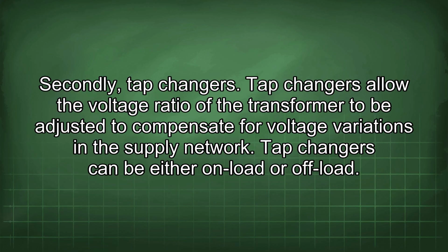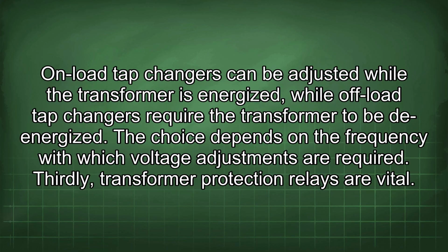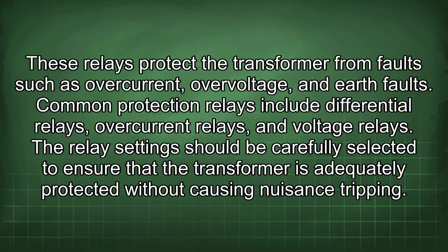Tap changers can be either on-load or off-load. On-load tap changers can be adjusted while the transformer is energized, while off-load tap changers require the transformer to be de-energized. The choice depends on the frequency with which voltage adjustments are required. Thirdly, transformer protection relays are vital. These relays protect the transformer from faults such as overcurrent, overvoltage, and earth faults. Common protection relays include differential relays, overcurrent relays, and voltage relays. The relay settings should be carefully selected to ensure that the transformer is adequately protected without causing nuisance tripping.